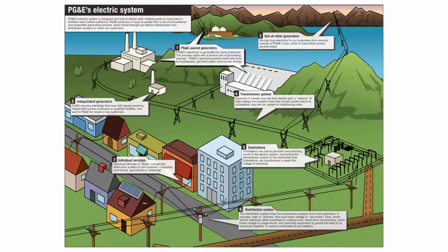And so these two things combined are changing the way that our grid operates and when demand is needed and when it's available. So what our project is trying to do is say: before we would say we can only allow a certain amount of power to flow through the system based off a very conservative assumption, but that conservative assumption is true 99% of the time.